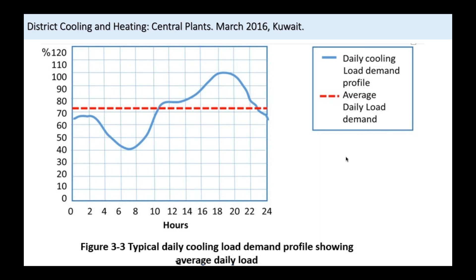This is the advantage of district cooling. Not only is the sum of all the cooling much less than the numerical sum of each, but you can also store energy by operating on a constant average load across the day and then using this energy at on-peak time when it's most needed. So your plant can be much smaller than one designed for the different loads put together.